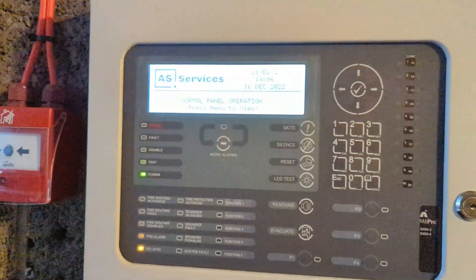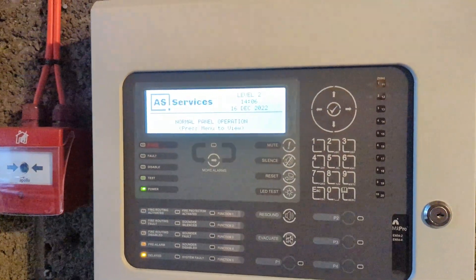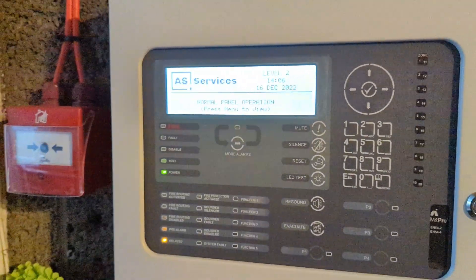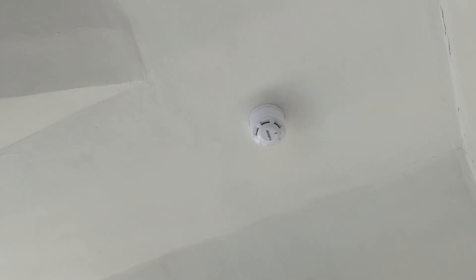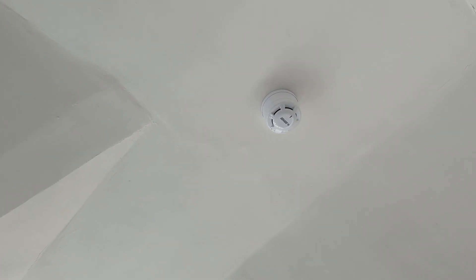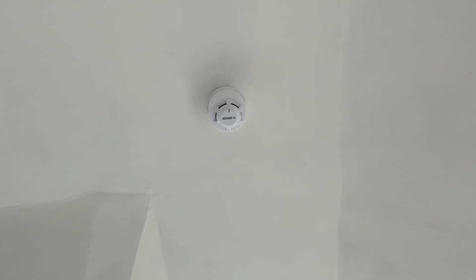We're going to test the first device — there is now a wireless detector fitted as well, instead of just sounders. So there's a sounder in the bathroom, and then we have the wireless detector which you'll see. You would have known about the device here in the living room. It's a bit of a high ceiling, and the thought behind it is to not put anything literally everywhere — but to put a detector here. There it is — an EMS fire cell optical. We'll give that a test and make sure the system works properly.